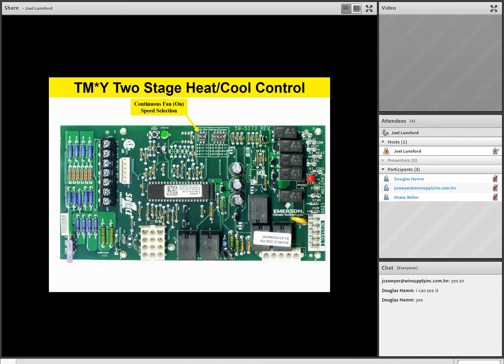So remember, team, whenever the board sees a G only call, so let's say the homeowner goes to the thermostat and flips the fan switch from auto to on, those dip switches will determine how fast the fan's going to run on continuous fan speed. Electrically, it's just a G only call from the thermostat. Based on the dip switch selection, you'll have either a low heat or high heat, low cool or high cool speed selection for your continuous fan. Are there any questions or comments on that?